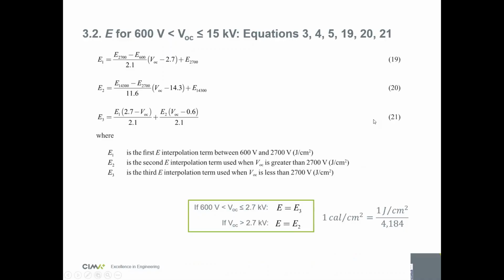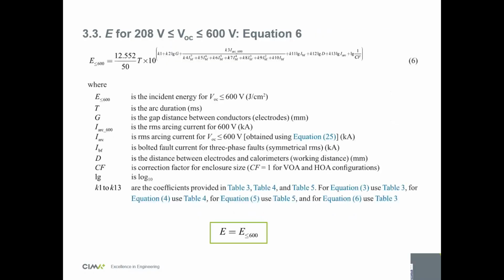So once you have the 3 energies calculated, then you need to interpolate them, calculating E1, E2, E3, and then your final energy. If you're below 2.7 kV, it's E3. If you're above 2.7 kV, it's E2. And then all these equations are in joules per centimeter squared, but if you want to convert it to calories, you just divide your result by 4.184, because that's the conversion factor for joules and calories. So that was energy above 600 volt.